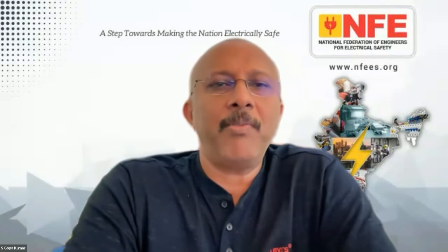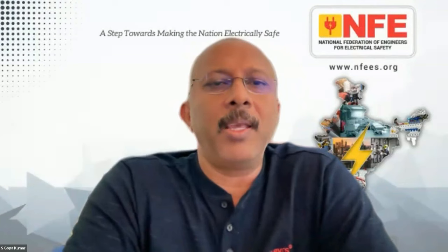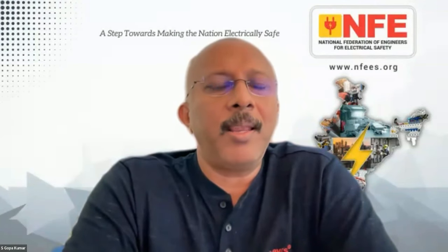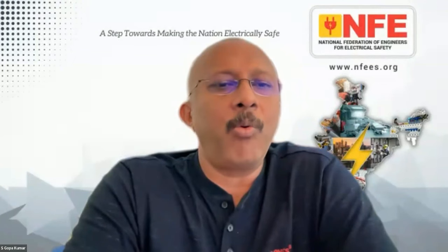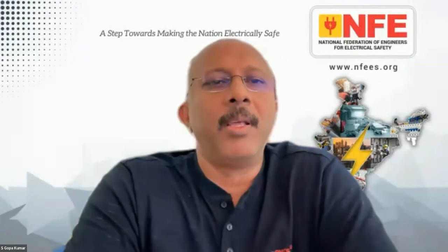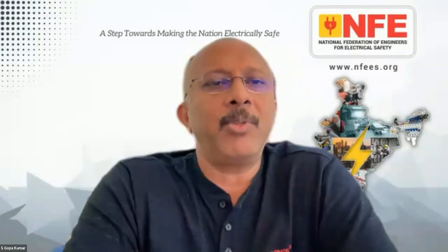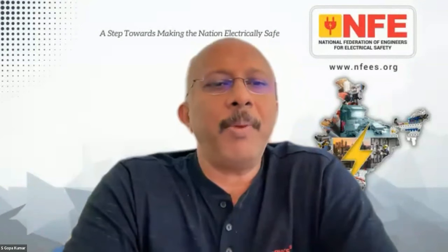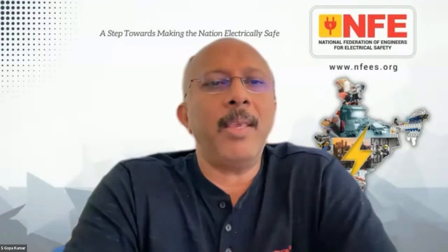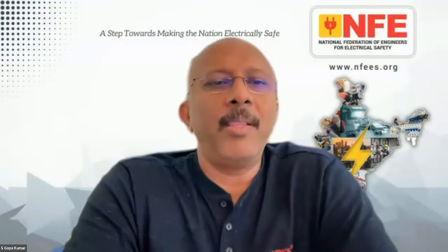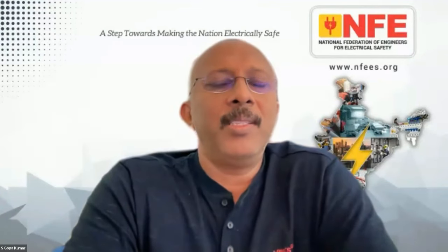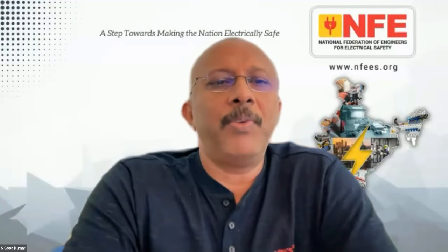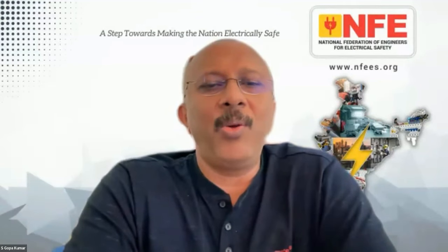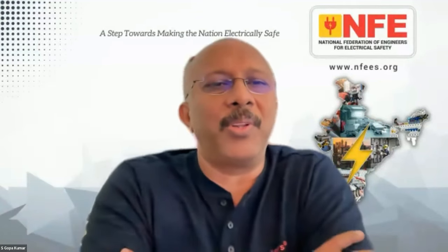For example, most of the machines, let's say the biomedical equipment, the European machine manufacturers in their catalogs very clearly explain how to make equipotential bonding. But the same supplier, when it comes to India, asks for a separate connection to a separate earth electrode, and they call this clean earthing. This is a big problem which we are facing all over India. What's your opinion about this?